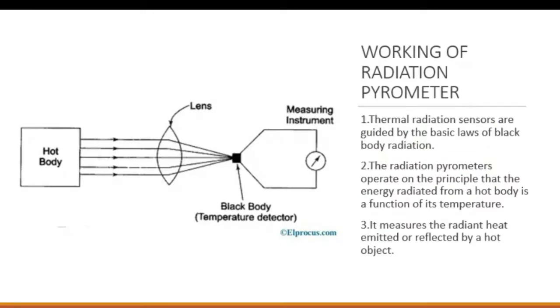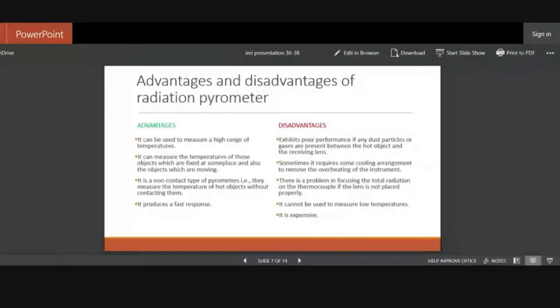Next slide. Working of a radiation pyrometer. So let's see its working. When the hot body emits radiation, the lens focuses it onto the black body or temperature detector that converts the radiated energy into electrical energy for the measuring instrument. The measuring instrument detects the temperature. Thermal radiation sensors are guided by the basic laws of black body radiation. Radiation pyrometers operate on the principle that energy radiated from a hot body is a function of its temperature. It measures the radiated heat emitted by a hot object. Next slide. Over to you, Mallar.